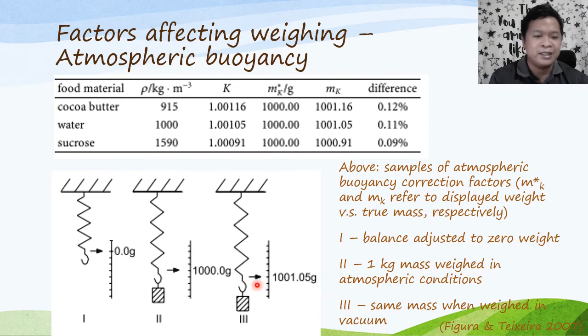Okay, so from that you can experimentally derive correction factors for it, no? So as you can see here, yun yung effect ng buoyancy, let's say on a spring scale, because if you're not in vacuum, the air is somewhat pushing it up para mas mababa yung deflection ng spring ever so slightly. Very important yung calibration natin, no? For our results. And what are the things that could affect our calibration? Definitely, if hindi regular yung calibration mo or balahura yung pag-calibrate mo ng balance, ay magkakamali yung actual weight. Okay, posible rin na faulty yung electronics or mechanicals ng balance.